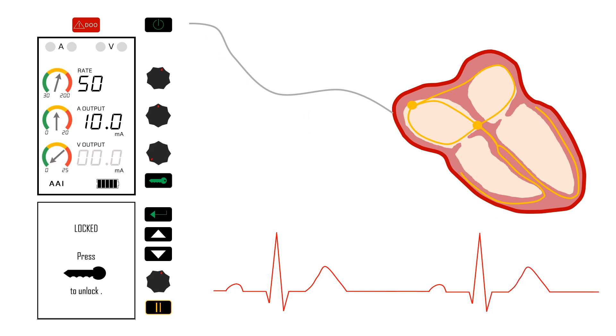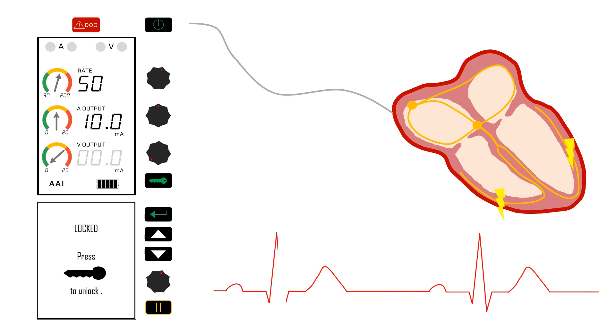Here, the pacemaker is in AAI with only an atrial lead, and the heart is conducting normally. The pacemaker is sensing the intrinsic atrial activity as before. Pacing is inhibited in response to sensing, as the mode is AAI — the I stands for inhibit. The pacemaker will not pace the heart if it senses underlying atrial activity.